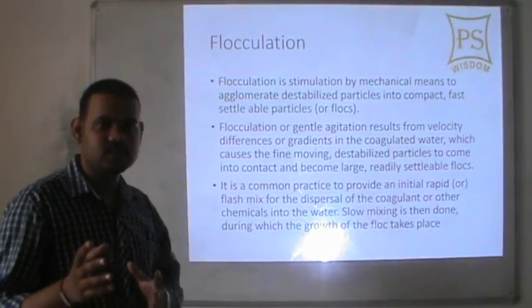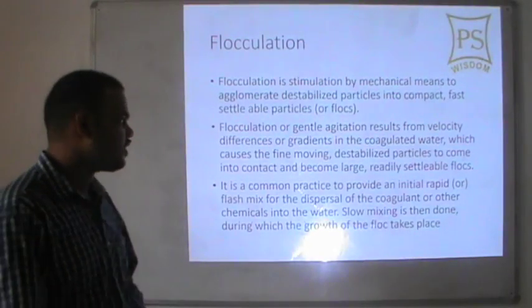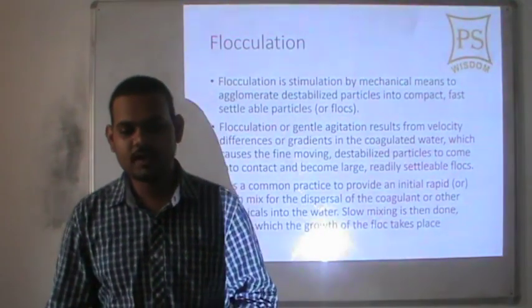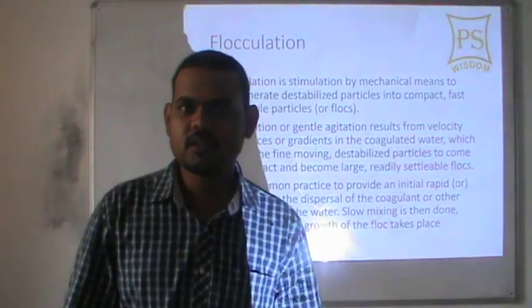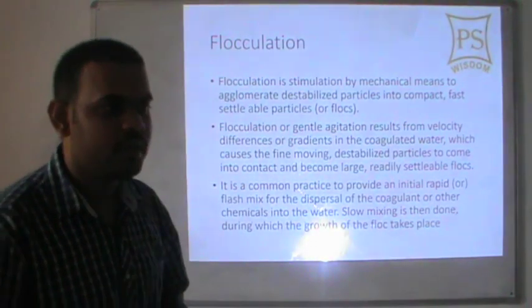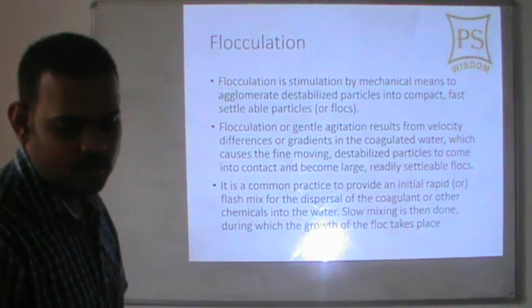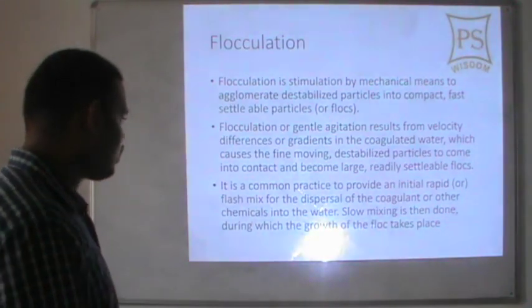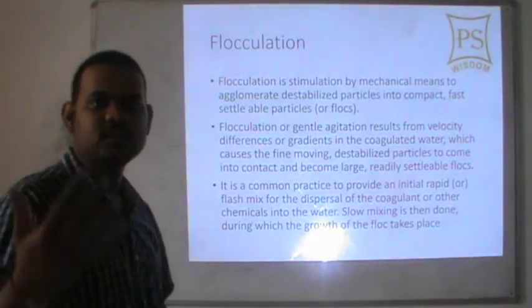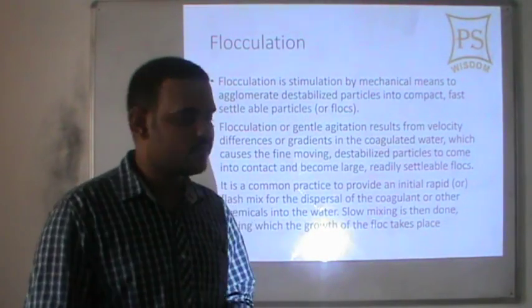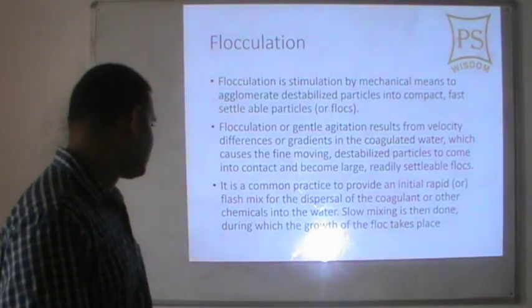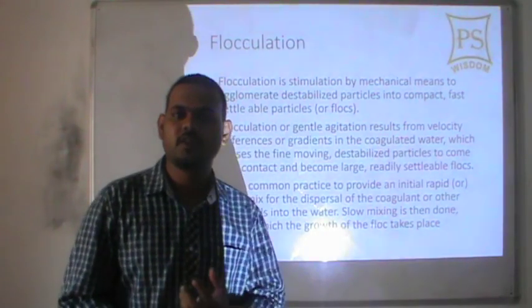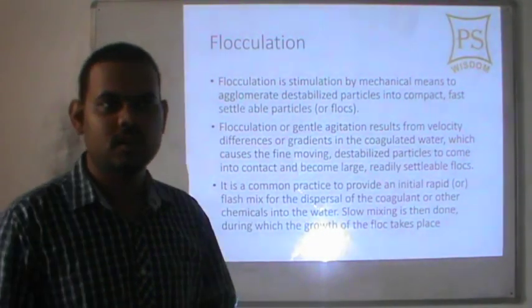Gentle agitation results from velocity differences or gradients in coagulated water, which causes the fine moving particles to come into contact and become large, readily settlable flocks. It is common practice to provide initial rapid or flash mixing, in which coagulants are mixed with water rapidly for dispersal into water. After this rapid mixing, slow mixing is done, during which the growth of flocks takes place.